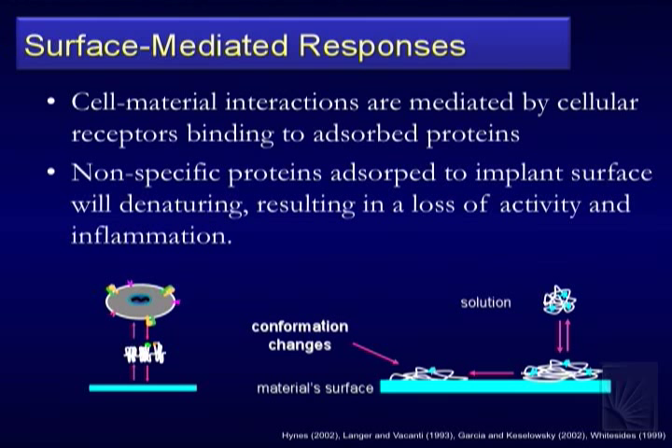There's an added challenge in the bioelectric system: I'm pushing charge in and out — there are potentially oxidation-reduction reactions at the electrode. Somehow pushing electrons into ionic movement changes the surface potential. Even if you put a great non-fouling coating on, you're going to have potential changes that become an issue for proteins — sometimes a positive surface, sometimes negative. So you have more than just a plain surface to get right; you have an active surface that's always changing.